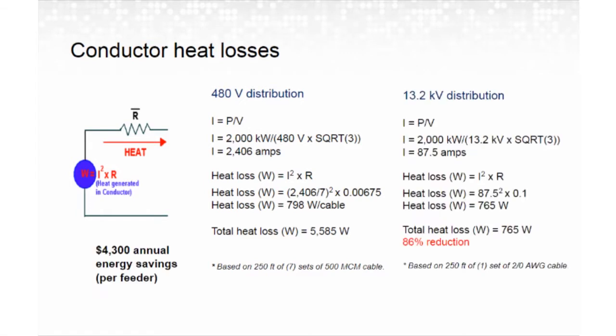One thing to do to help lessen that loss is use medium voltage. Medium voltage has a lot less current flowing through that same conductor. So that same 2,000 kW load is only 87 amps at 13.2 kV, which results in a total loss of only 765 watts. So it's an 86% reduction in heat loss from that cable by going to 13.2 over 480. And what does that amount to? Well, it's about $4,300 of annual savings, which doesn't seem like a lot. But if you look at a data center, which may have multiple paths, multiple redundancies, multiple feeders, that can start to add up really quick.